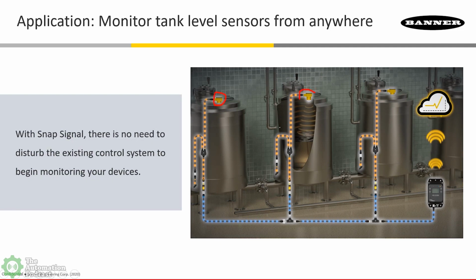What we're able to do is take that 0 to 10 volt signal and convert it over to, in this case, a unified serial RS-485 protocol, then bring it back to our DXM 1200 controller and push that data to the cloud. In this application, they wanted text message alerts if their raw material fell below a certain threshold, notifying personnel throughout the factory that the liquid in their tanks was running low.